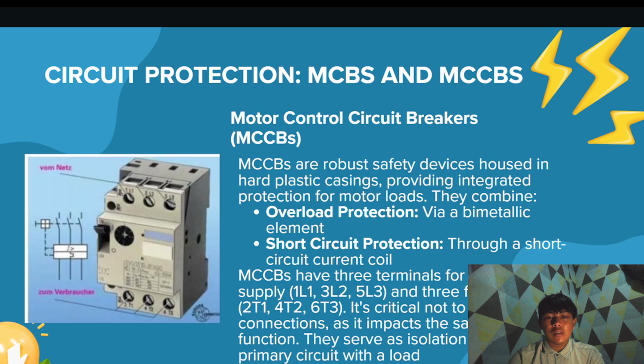MCCBs are robust safety devices housed in a hard plastic casing, providing integrated protection for motor loads. They combine overload protection via a bimetallic element and short circuit protection through a short circuit current coil. MCCBs have three terminals for the power supply, 1L1, 3L2, 5L3, and three for the load, 2T1, 4T2, and 6T3. Each connection is critical, as it impacts the safety device function. They serve as isolation for the primary circuit with the load.